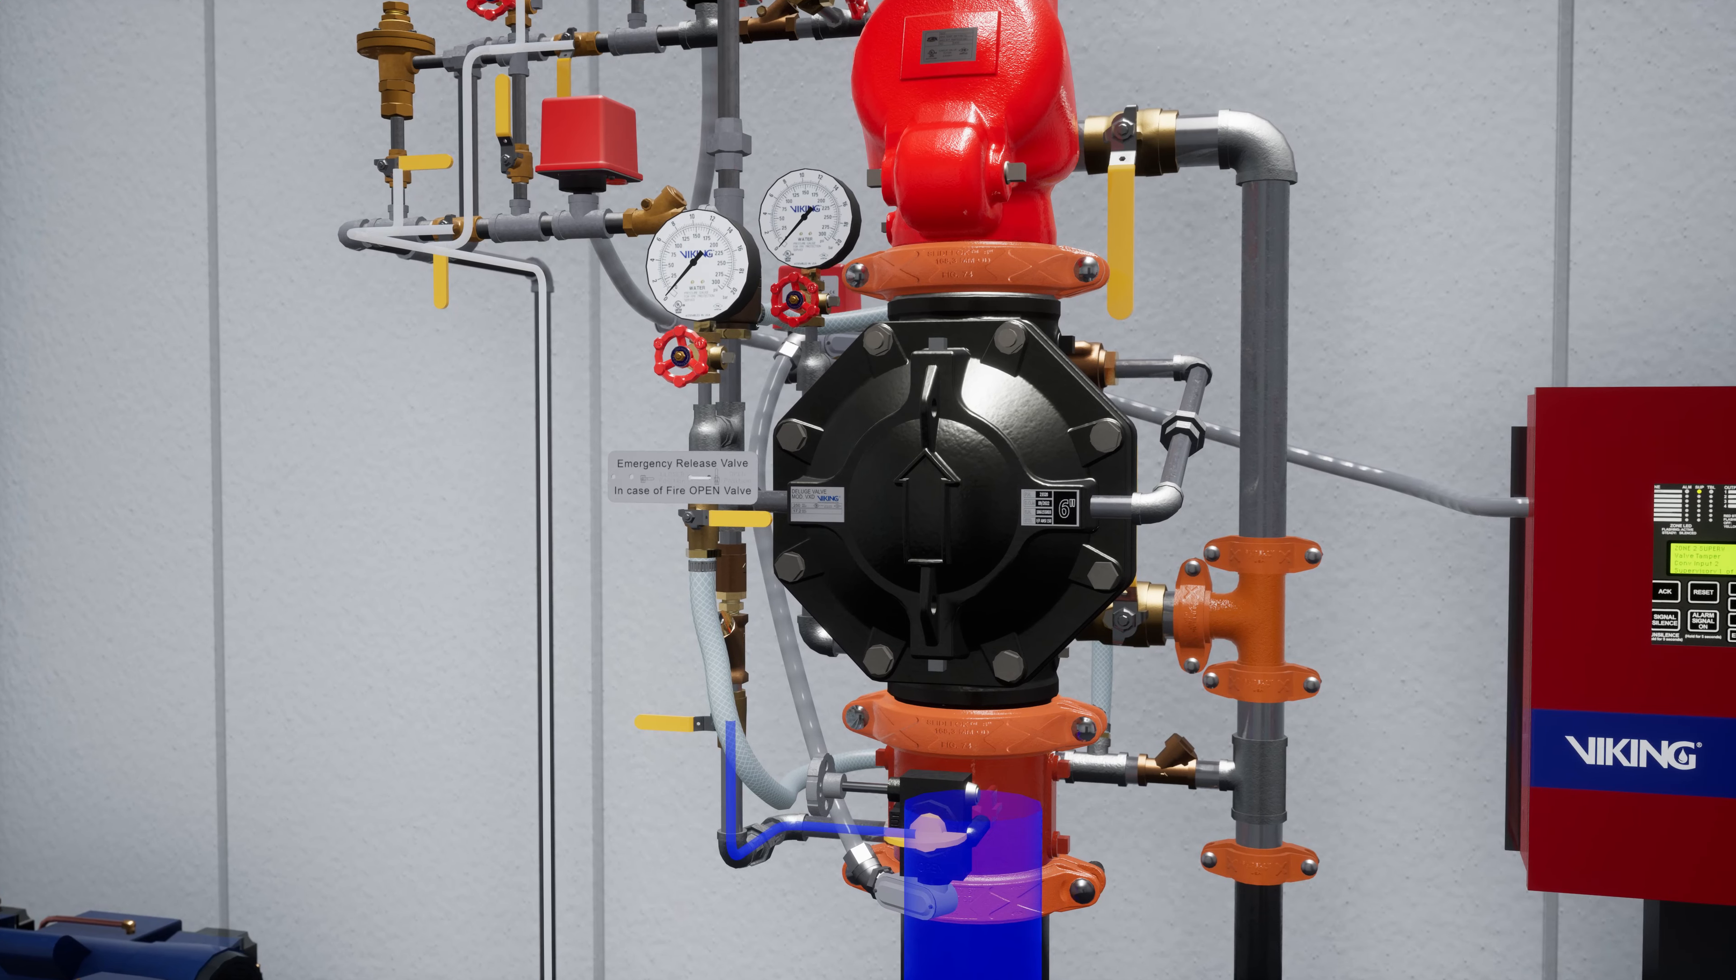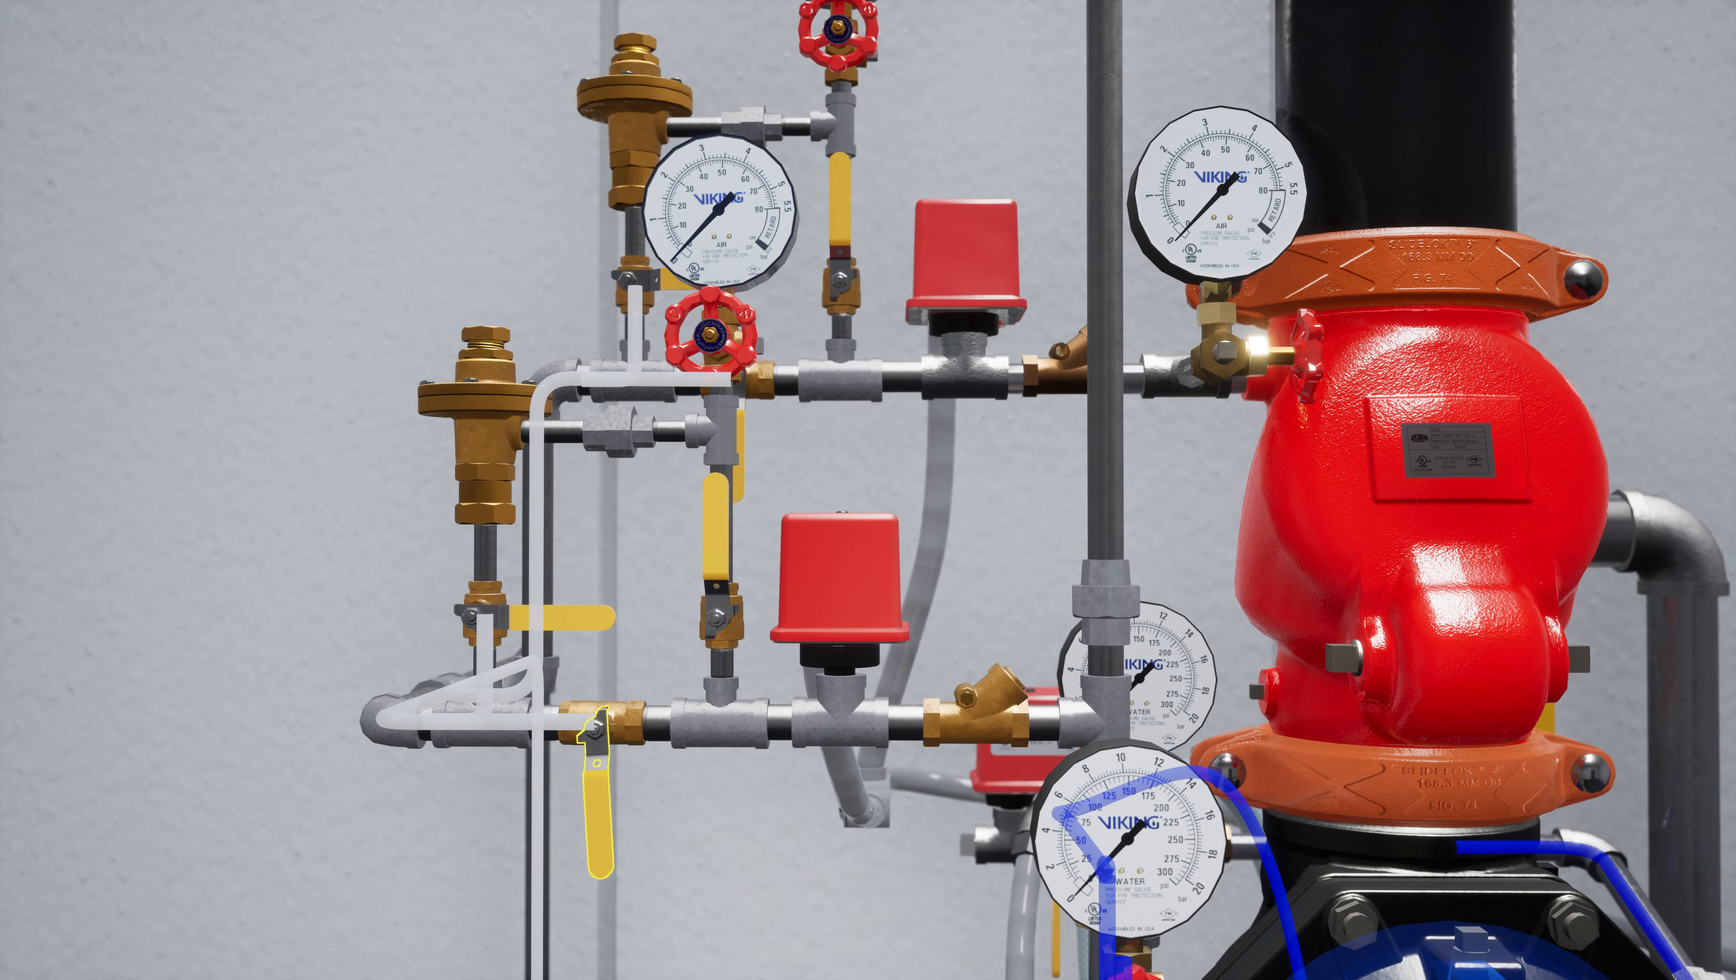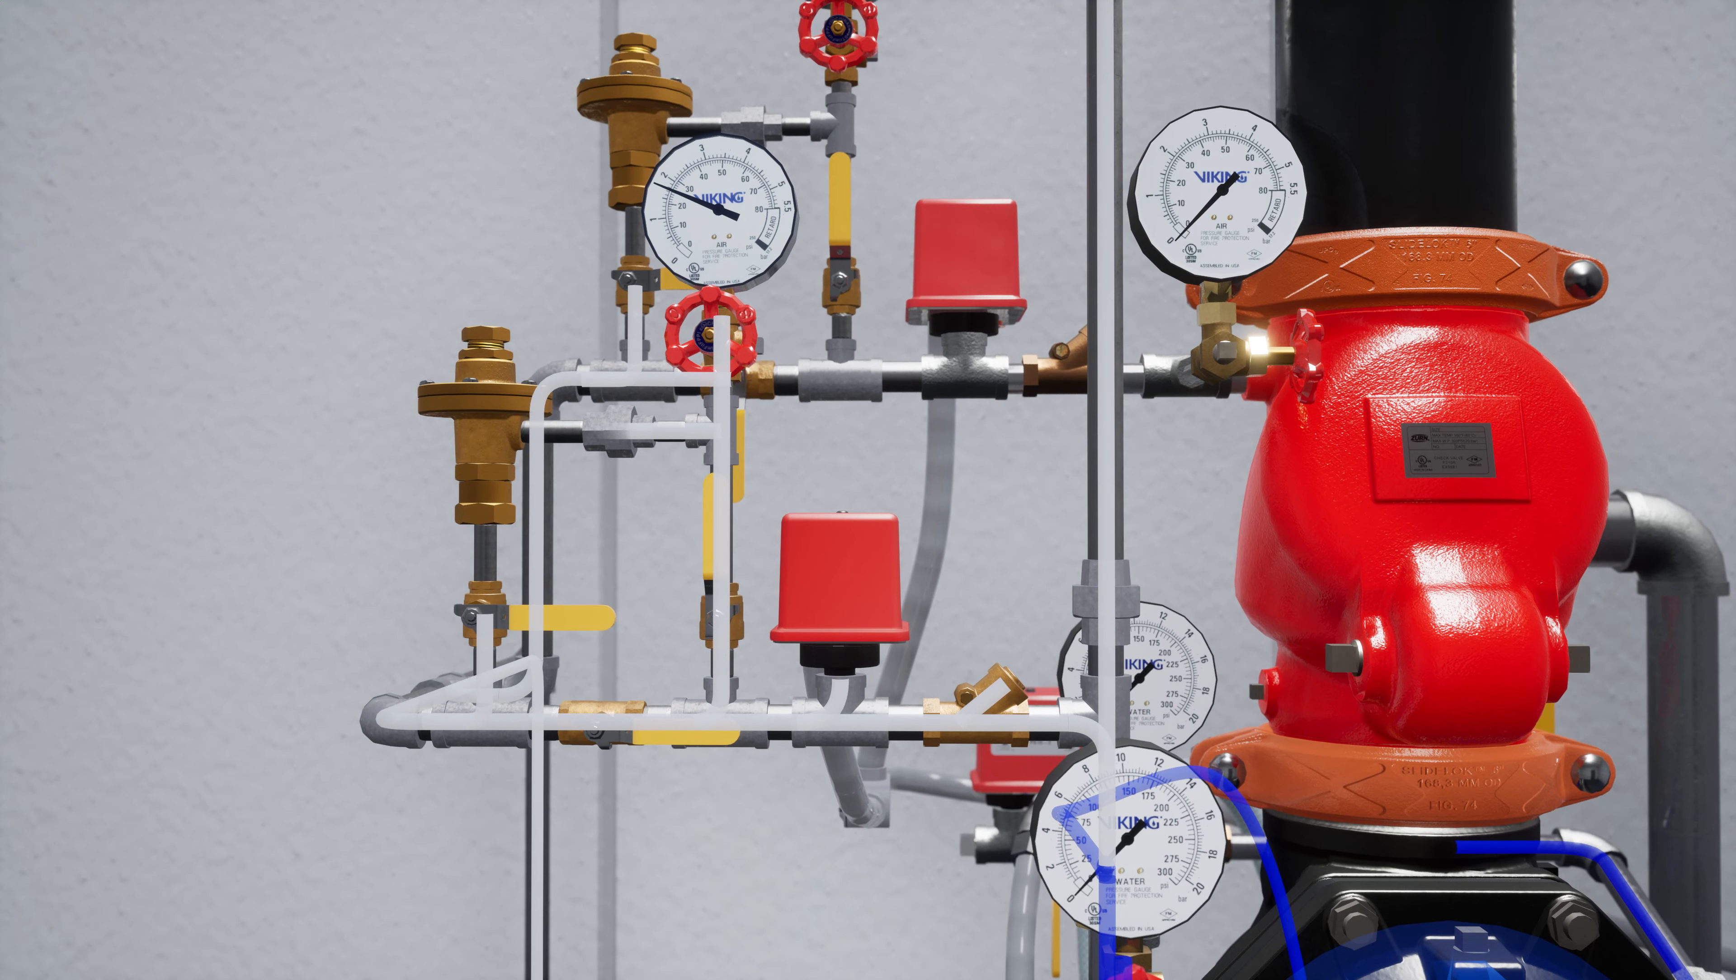Now open the priming valve. Priming water will discharge from the pneumatic actuator to the drain. We can start introducing air to the dry pilot line by opening the air bypass valve on the air maintenance device that leads to the dry pilot line. Once the release line air pressure is within 5 psi of your target air pressure, close the air bypass valve and open the ball valve below the air maintenance device to finish filling the release system.